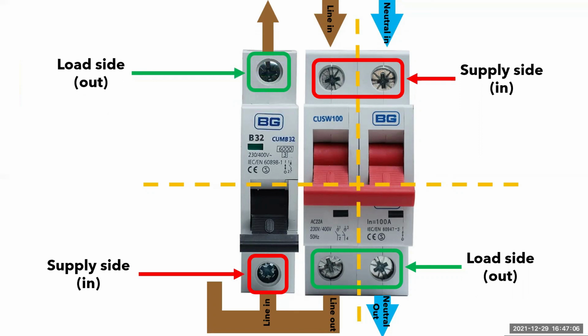Because again, if you were testing and you weren't able to isolate the supply to the consumer unit, this supply side would be live. So there's no good testing there, and the load side would be dead. Obviously, in assessment situations, there would be no power to the supply side. They would never liven that up for apprentices or people in training. So you'll test at this point, but there won't be any voltage there. So be very, very careful.